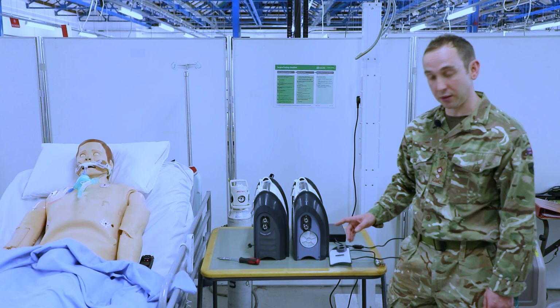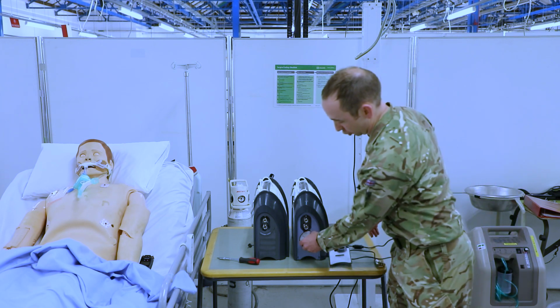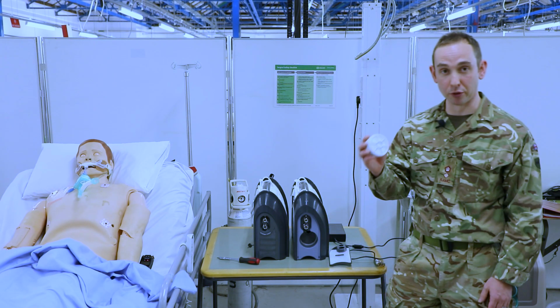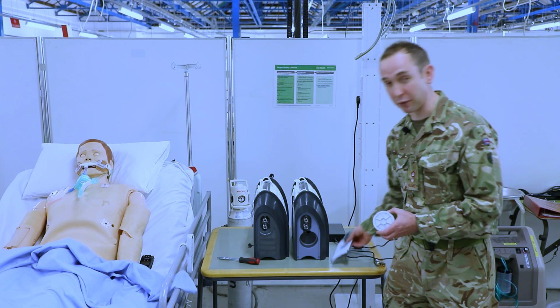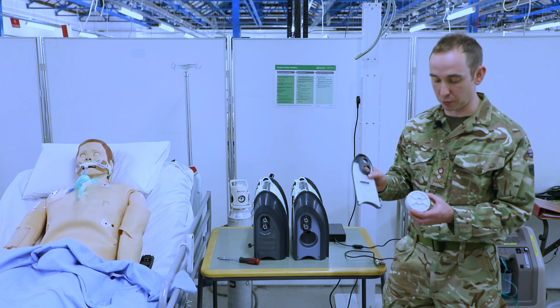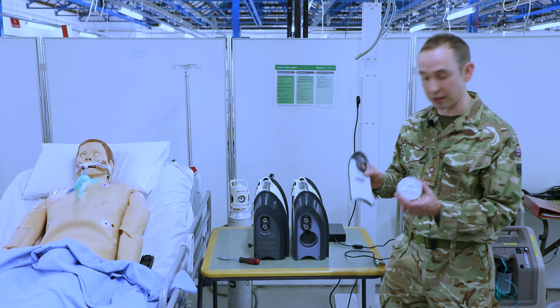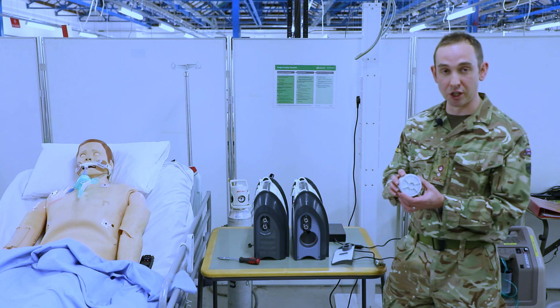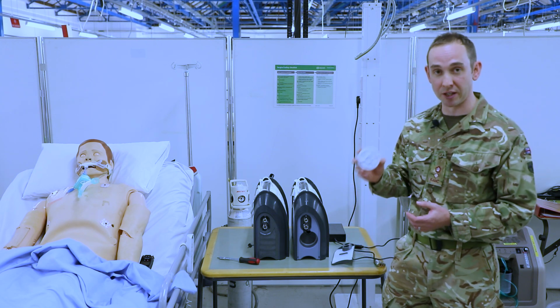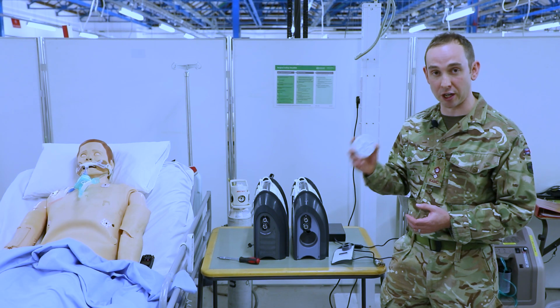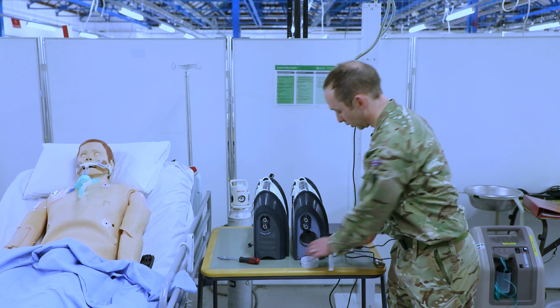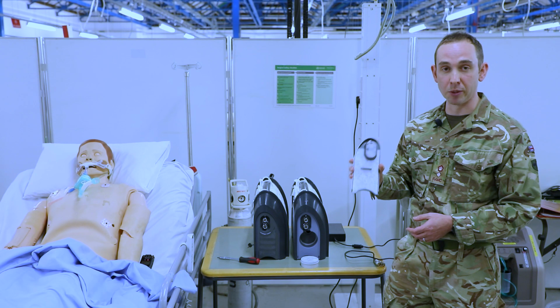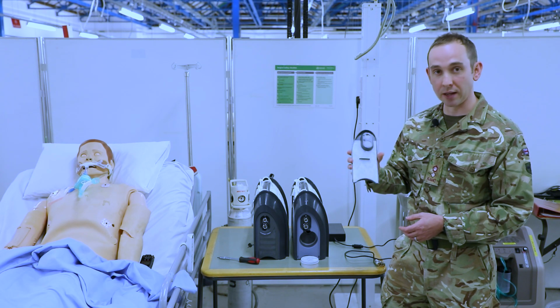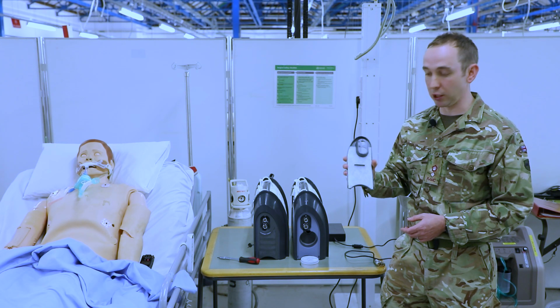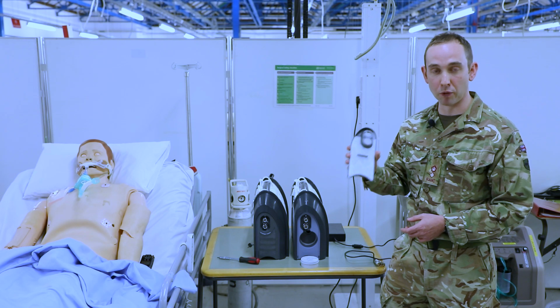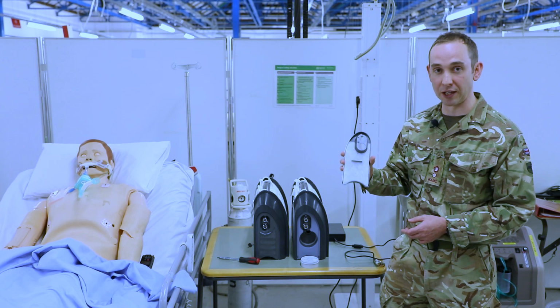On receiving the machine, please ensure that you do have a HEPA filter attached, and if required, if it's missing, then order a filter pack which has an NSN number and you'll get both filters in. The HEPA filter should be changed yearly, and this is usually done by MDSS, but you might have local procedures where it is changed by yourselves. The coarse filter again should be changed every year, but again in certain climates like dusty or dirty areas this might be changed more regularly and will be dependent on local SOPs.